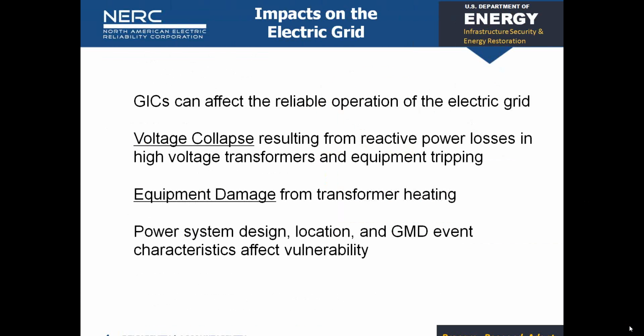The current flow in the transformer causes additional reactive power demand, so the transformer is working harder, but it can also cause hotspot heating or circulating currents inside the transformer that will lead to very localized heating effects, and that can cause transformers to be damaged or have their lifespan reduced. All of these conditions, though, are really dependent on a number of factors, like the design of the system, where it's located in the topology, and the very GMD characteristics that the system is experiencing.